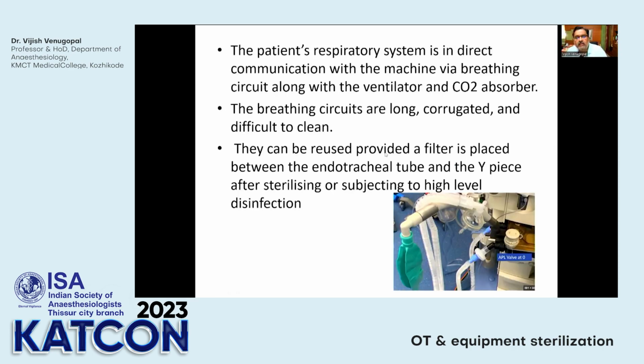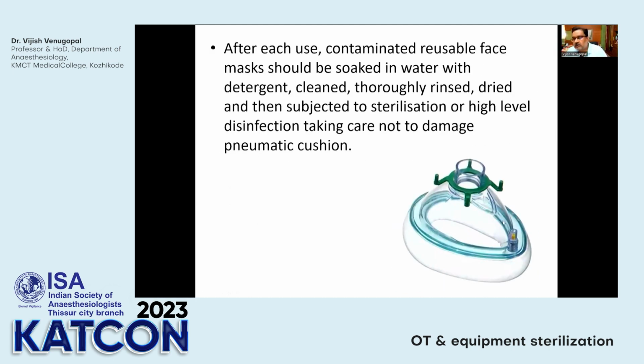And it should be reused only if you have used the filters. You should have used a bacterioviral filter at the expiratory end, and this filter should be changed. Now, the face mask, it is being reused. We all know the reusable face mask. It should be soaked in water and detergent, cleaned thoroughly, rinsed, dried, and then subjected to sterilization or high-level disinfection, taking care not to damage the pneumatic cushion. So, if you use one face mask on a patient, for the next case you should not use the same one. Wash them thoroughly and use high-level disinfection.